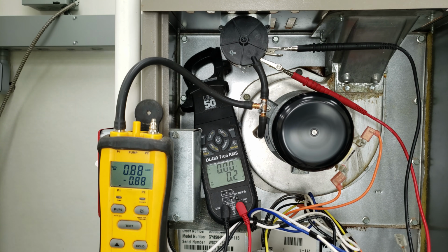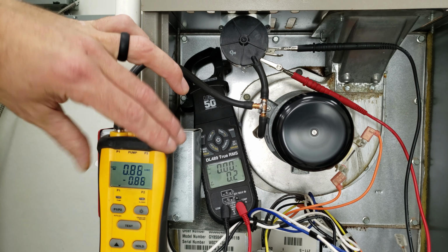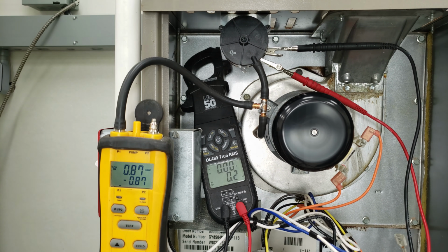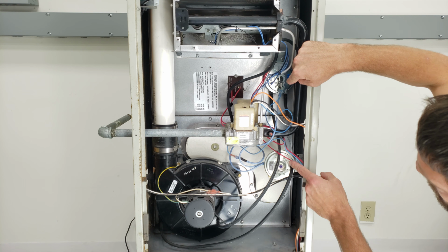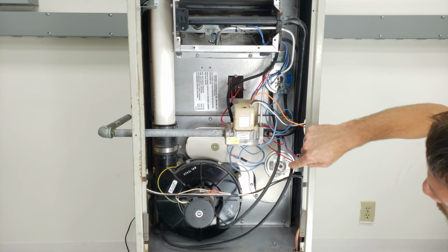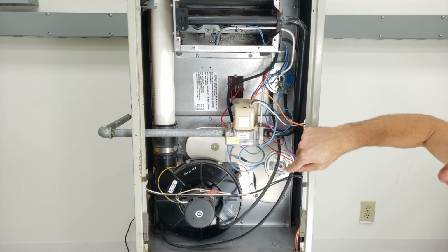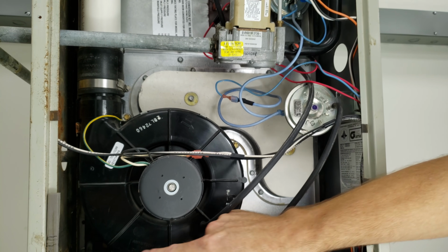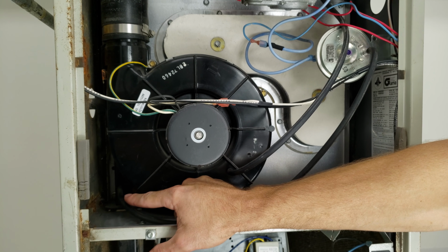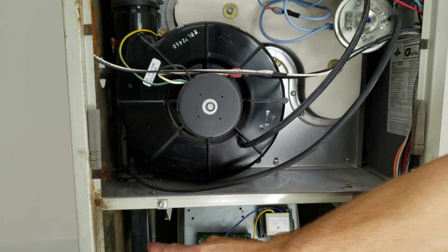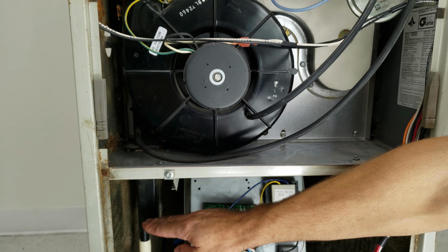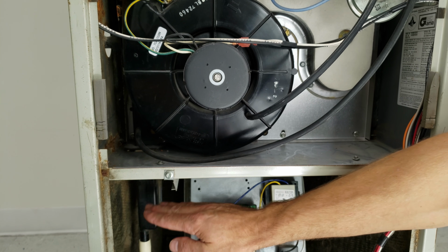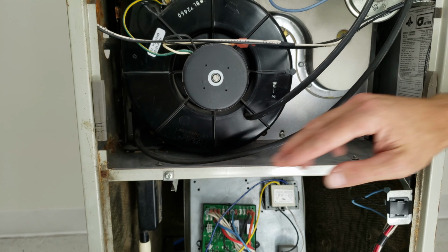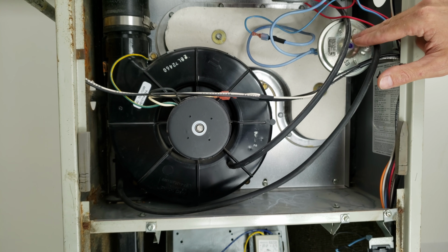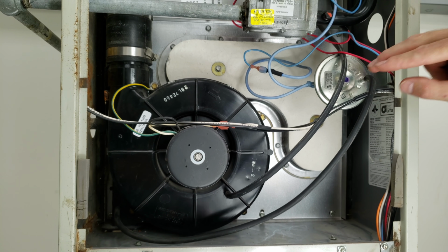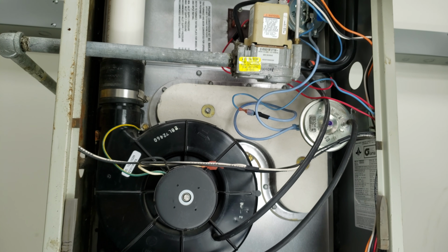Now we're going to move on to measure the pressure differential across a 2-port pressure switch. This furnace right here has two pressure switches. This one's a 2-port pressure switch, and here we have a single-port pressure switch. And this tube right here is connected over to the inducer motor housing, and this is monitoring if this condensate trap right here gets clogged with water. So if the water level rises above this port right here, this pressure switch is going to open up the electrical circuit. And so now we're going to move up and explain the 2-port pressure switch.